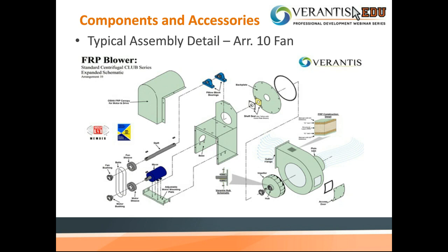So what we like to do, especially for some of you novice people out there, is show an exploded detail of a fan. This is an arrangement 10 style, so this is where the motor is going to sit within the base itself. This shows how all the bits and pieces go together. Let's start right in the middle with the actual base itself, and look to the left of the base. There you have the motor, which is sitting on top of an adjustable base that will raise up and down. And then you'll see the drive set.